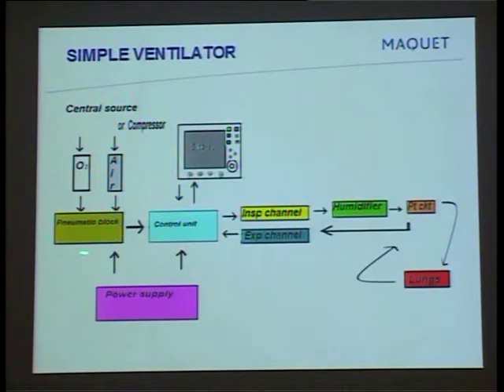That's why we have a pneumatic block inside the ventilator. These pneumatic blocks have several pressure reduction valves inside the machine. We keep reducing the pressure step by step, and then we store it in a tank, which we call a reservoir. Then we have a control unit. Whatever input you want to give, you can feed it in. The control unit will take the input, and then produce whatever output it has to produce. It will control all the components of the equipment. It acts like the motherboard in your computer.